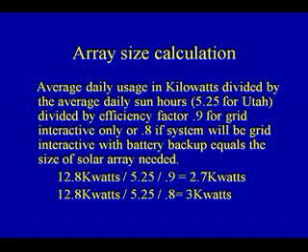Now, the efficiency factor, so that you understand that, are those losses in the system. For example, an inverter is not 100% efficient at converting DC power to AC power. Most of them run around 95 to 97%. Also, there will be voltage drop losses in the system caused by the wiring, and typically those are held to a maximum of 2%. Also, you will get some loss of power production caused by dust on the panels over the course of a year.